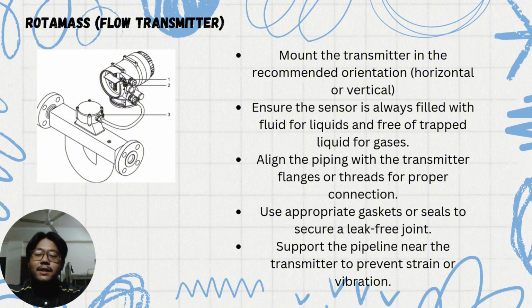Lastly, the installation has several steps. First, mount the transmitter in the recommended orientation, horizontal or vertical. Then, ensure the sensor is always filled with fluid for liquids and free of trapped liquid for gases. Then, align the piping with the transmitter, flanges or threads, for proper connection. Use an appropriate gasket or seals to secure a leak-free joint. And lastly, support the pipe line near the transmitter to prevent strain or vibration.